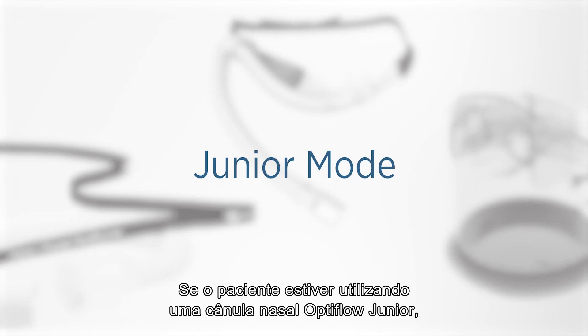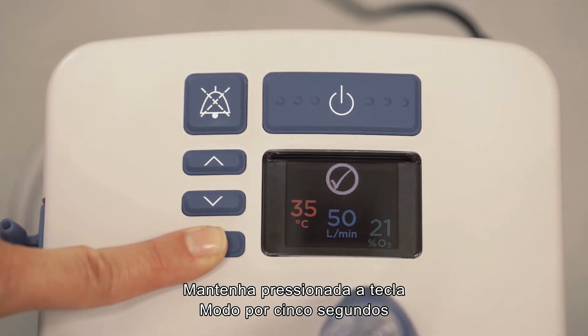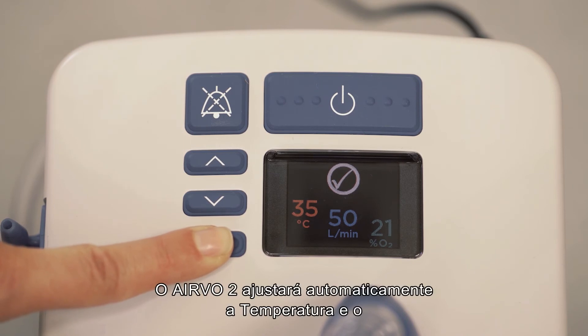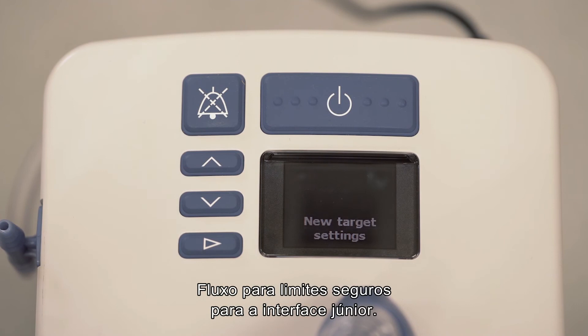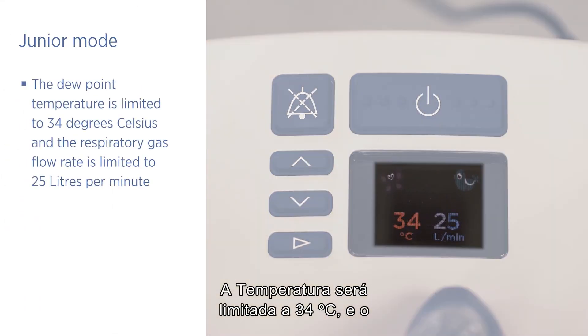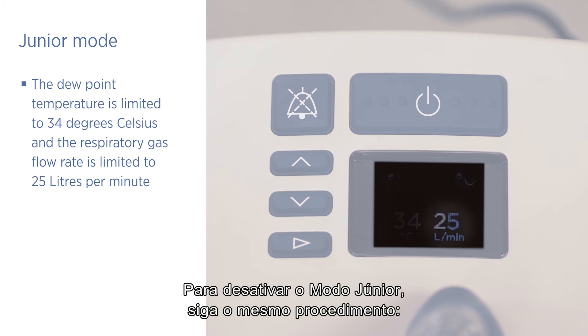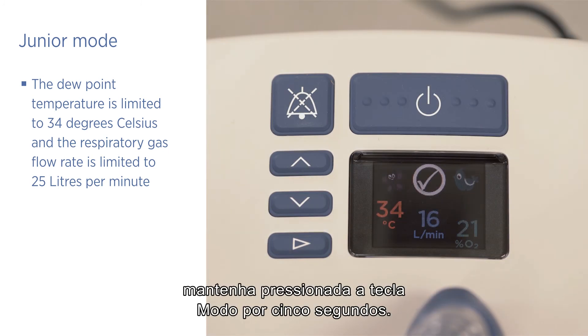If the patient will be using an OptiFlow junior nasal cannula, you must activate junior mode. Press and hold the mode button for five seconds until the junior mode symbol appears. The AIRVO 2 will automatically adjust the dew point temperature and gas flow to safe limits for the junior interface: the dew point temperature is limited to 34 degrees Celsius and the respiratory gas flow rate is limited to 25 litres per minute. To deactivate junior mode, follow the same procedure — hold the mode button for five seconds.